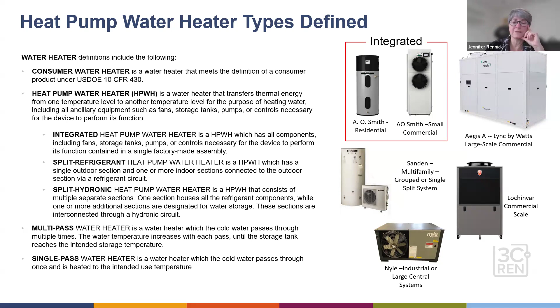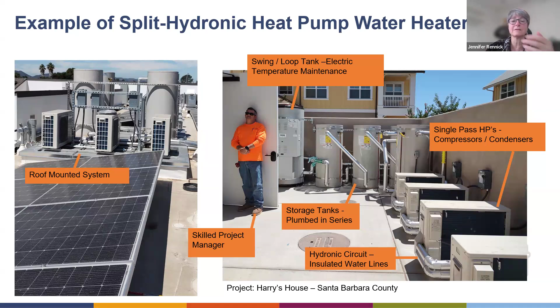There are also multi-pass and single-pass systems. To clarify with an example, a split hydronic heat pump water heater system is the Sanco 2 units, where you've got single-pass heat pump compressor units outdoors, and then they use a hydronic circuit.